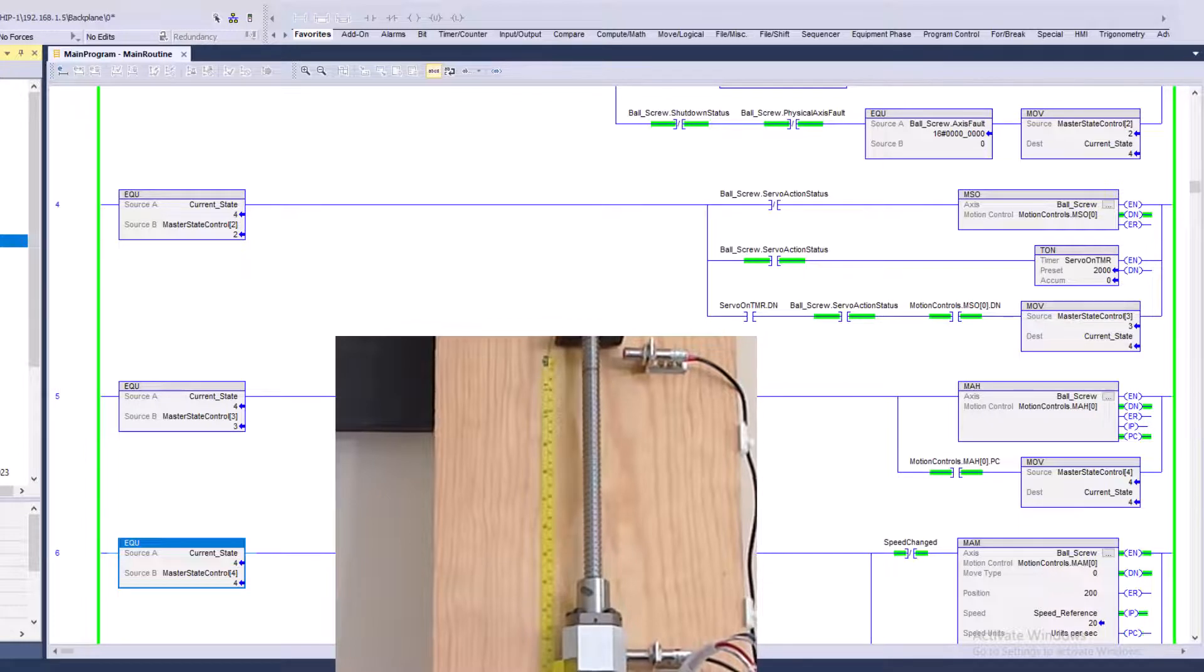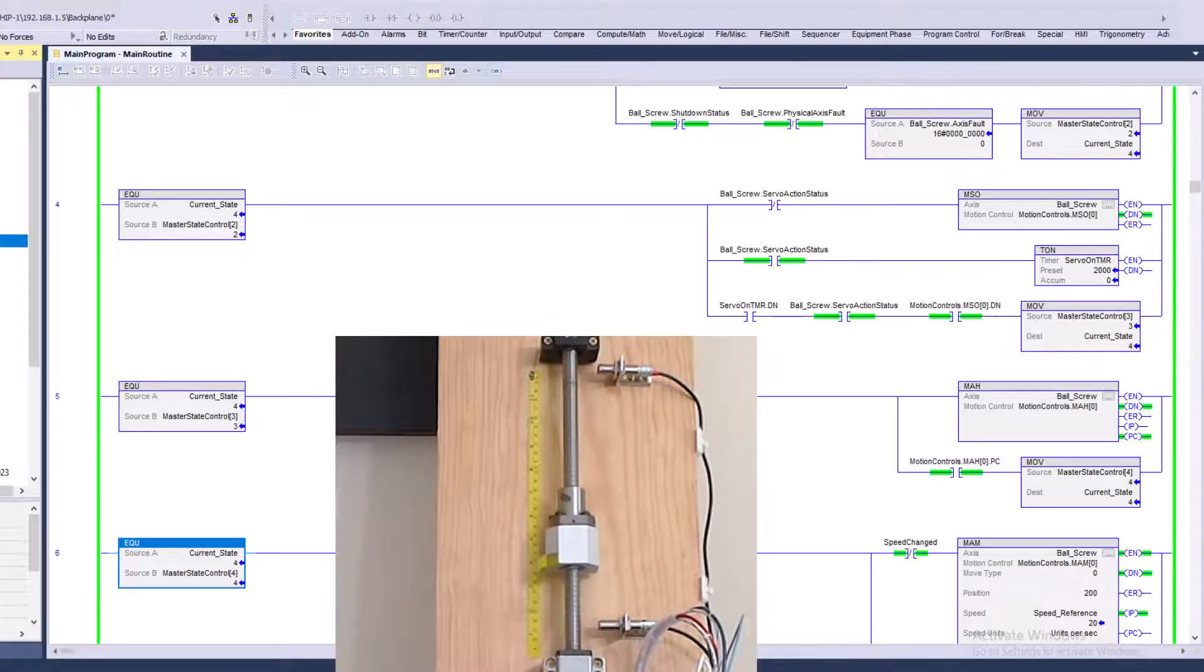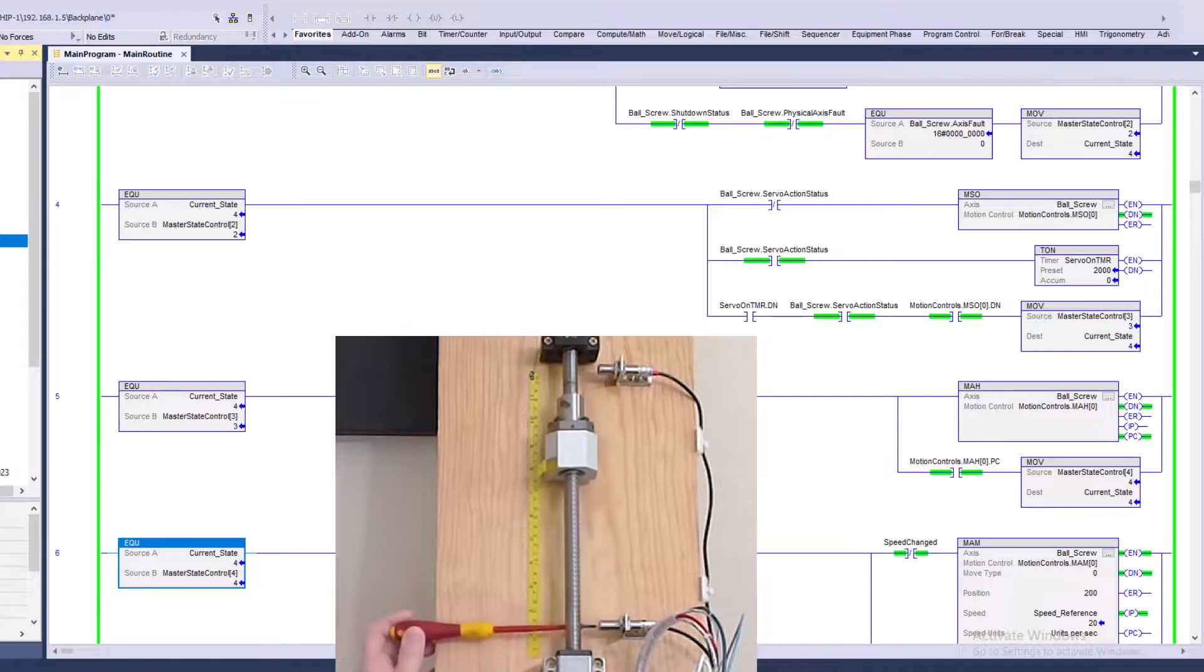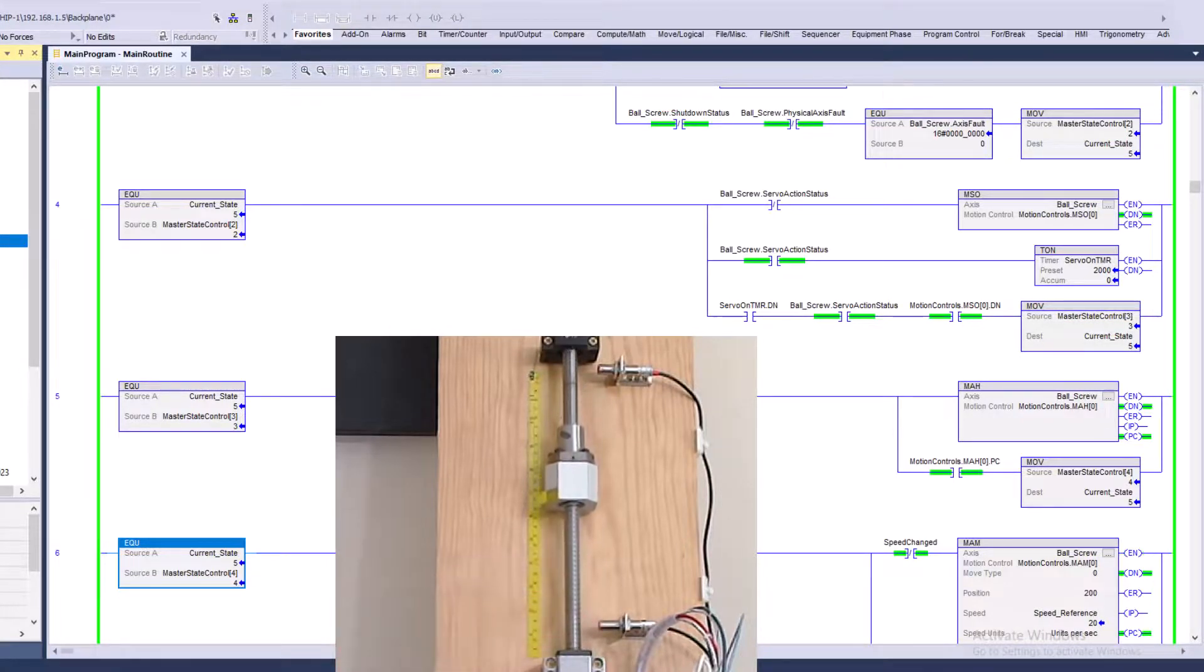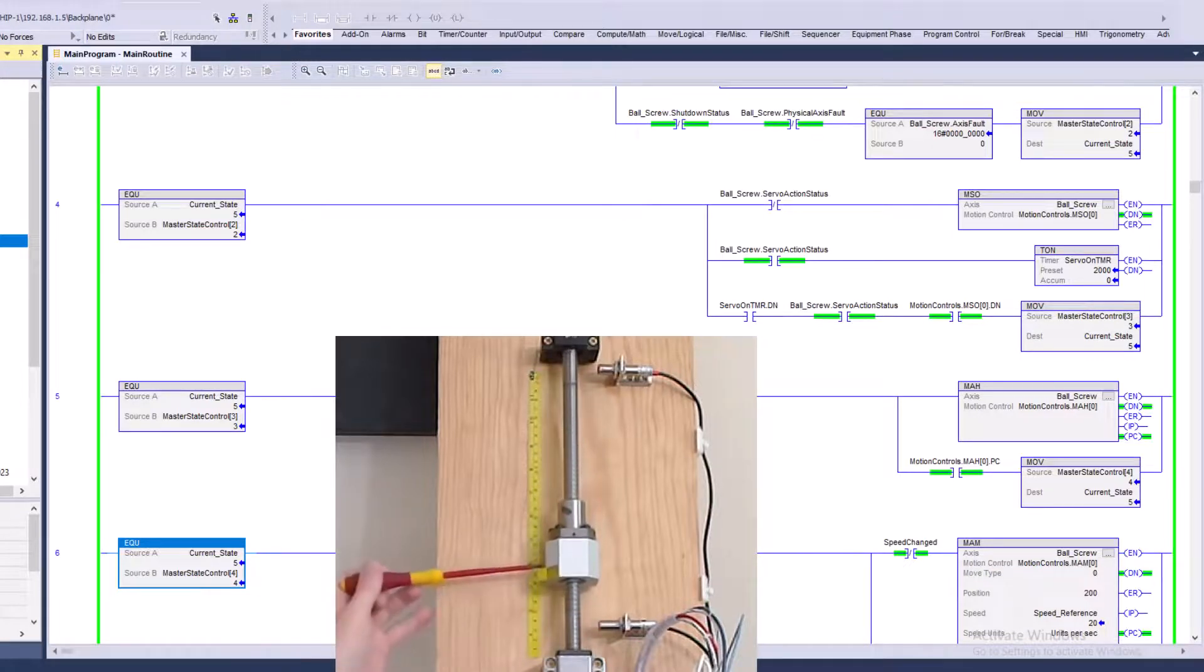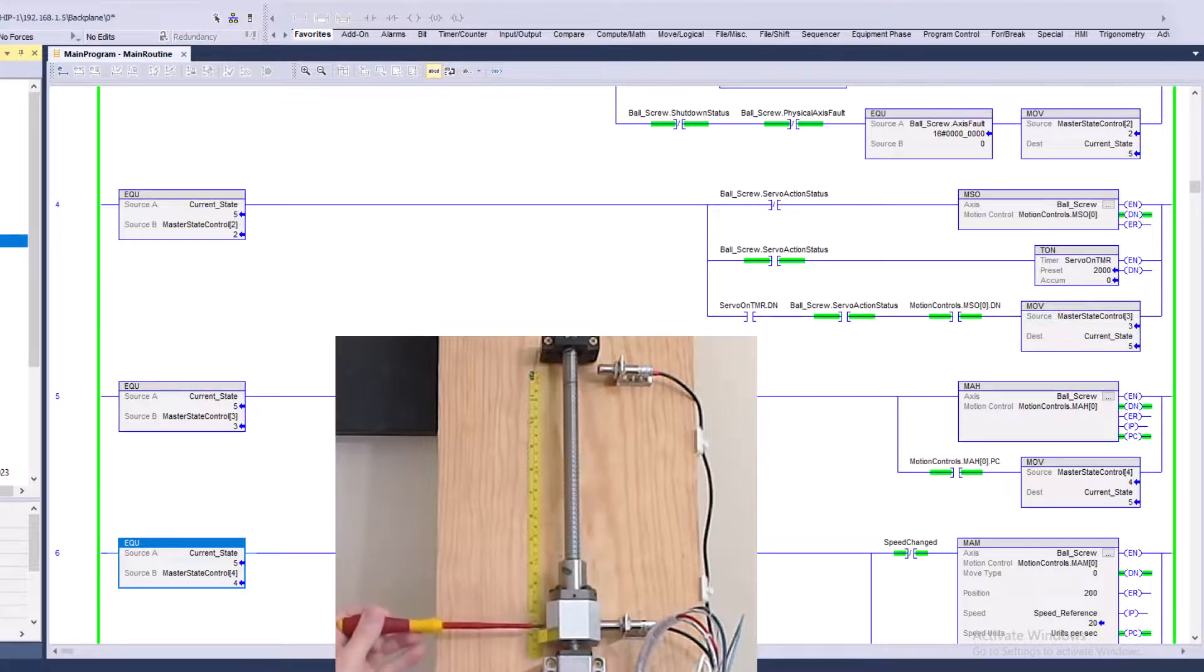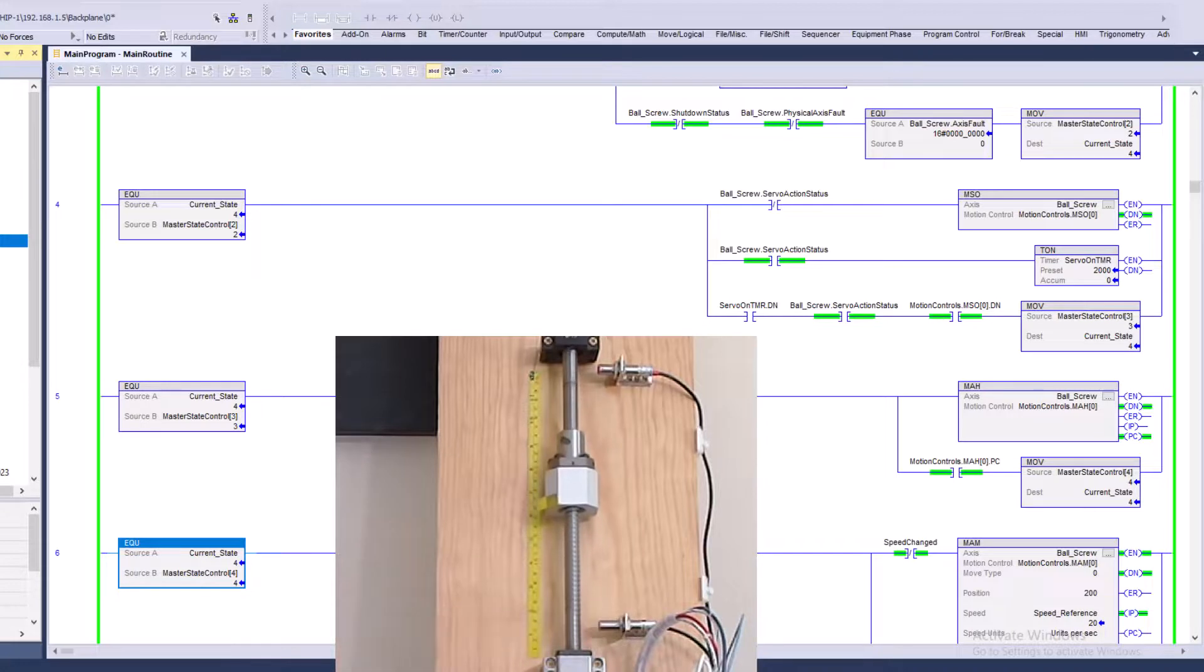So again, when it comes on down to it, I wanted to actually give a bigger view of how the system is actually wired. Again, the bottom one, this bottom prox right here is a home prox. It doesn't matter if it's not in the homing sequence, it can be made any given time. So that's how we're getting by with running past it right here is because it does not have to, it's not going to re-home just because I made that prox. It's only going to re-home if it's in the homing process and it hits that prox.